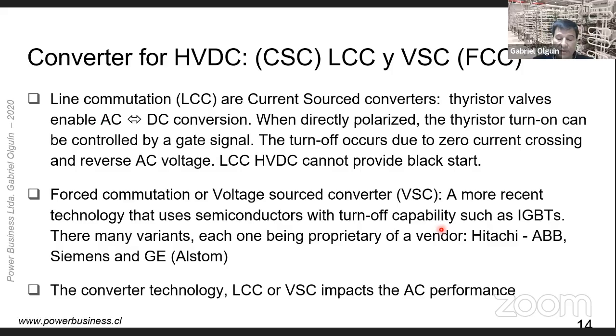For HVDC, there are basically two fundamental principles for AC to DC conversion and vice versa. HVDC LCC stands for line commutated converter and is the classic HVDC technology. LCC converters are current source converters that use thyristor semiconductors in arrays called thyristor valves. When directly polarized, the thyristor valve can be controlled to turn on with a low power pulse in the gate. The turn off, however, can only occur when the thyristor is reverse polarized and the current crosses zero. Therefore, LCC cannot provide black start capability, meaning that it cannot energize a passive network. In fact, for proper operation, an LCC converter requires a minimum short circuit level to ensure safe commutation of the valves and hence operation of the HVDC link.